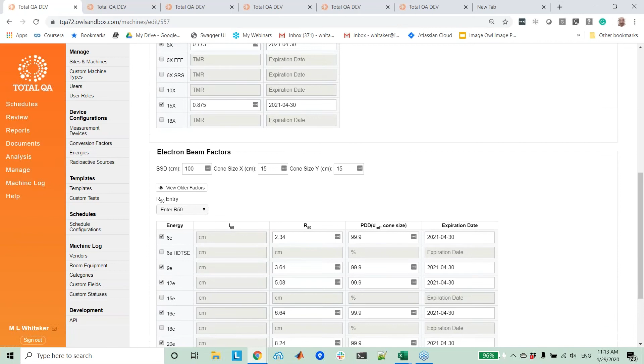And you can set the lead time on that ahead of the date, say a month or 2 months or something like that. And you'll see that in a few different places in the software. For the electron beam factors, we've got the SSD and what the cone size is. You've got another option here of how you're going to enter the R50 values.